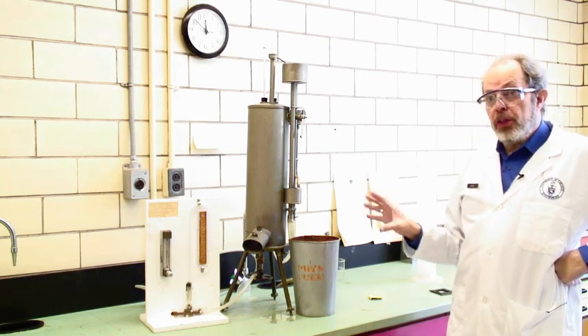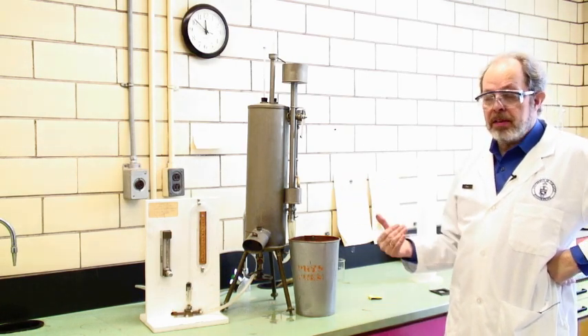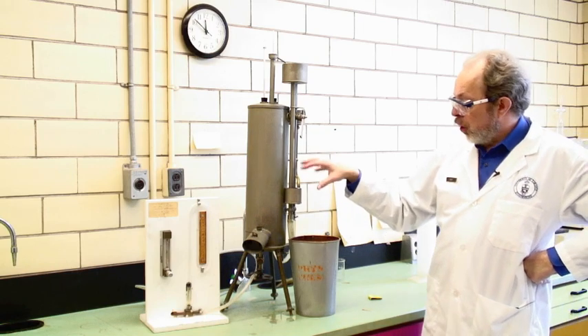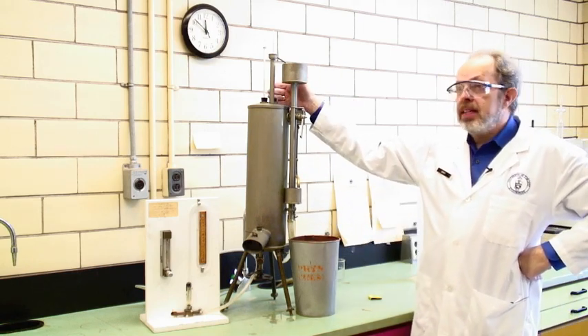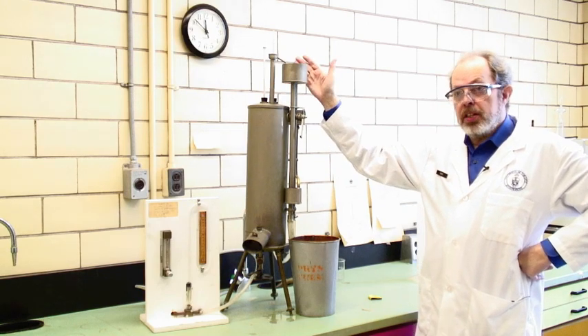You should do two or three of these runs and you can do them back to back to measure the amount of water that went through that was heated from the lower temperature up to the higher temperature.